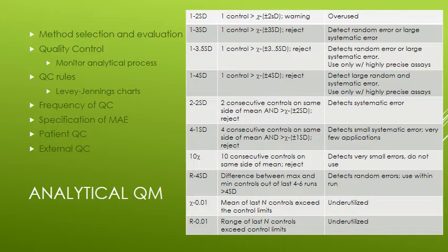So that's a lot. Then once you have it running, you have your normal, regular, daily quality control that you have to run. That helps you to monitor that, okay, I know it's supposed to work this way, and make sure that it keeps working that way. And when you do that, you're probably going to have lots more data that you're going to be looking at, and you're going to have Levey-Jennings charts that you'll be able to apply, hopefully, to the processing.